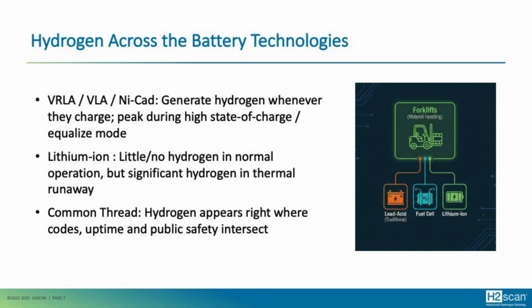So in the top section, with any kind of lead-acid battery or NiCad battery, hydrogen will be present as a normal gas that emits from the battery. Now, valve-regulated batteries are mostly recombinant, but if you overcharge them, they will release hydrogen. Vented lead-acid batteries, or VLA batteries, will emit hydrogen naturally as they charge. And then NiCad batteries will also, they're just like vented lead-acid batteries, except they're NiCad and they're also vented. So instead of a lead-acid battery, you have an alkaline battery.